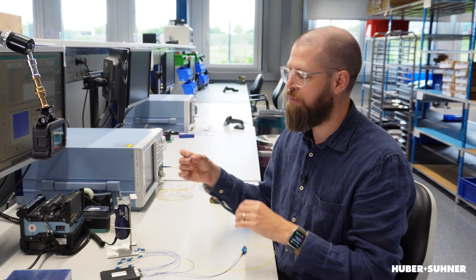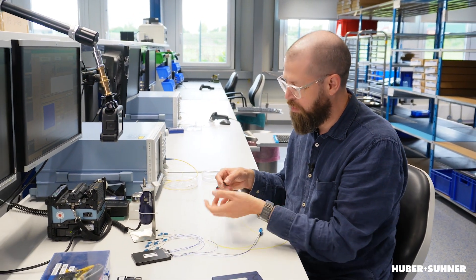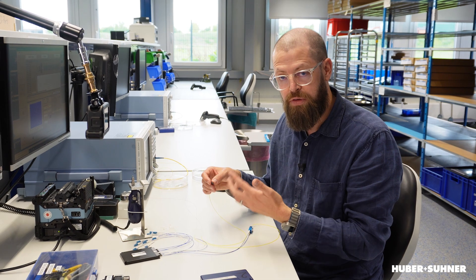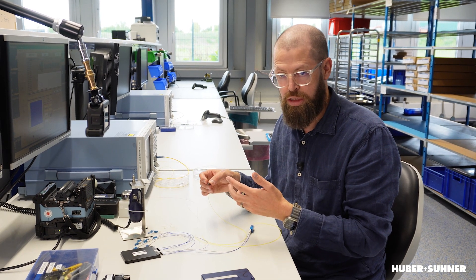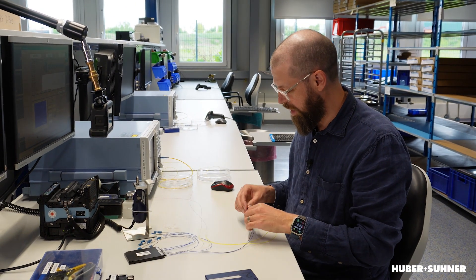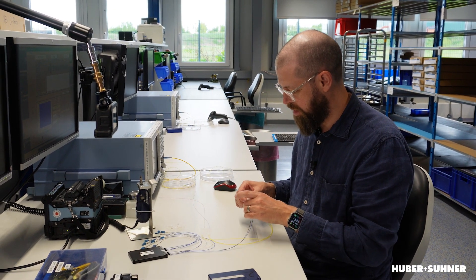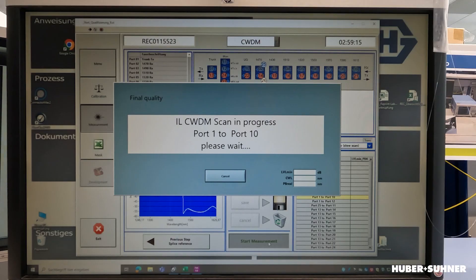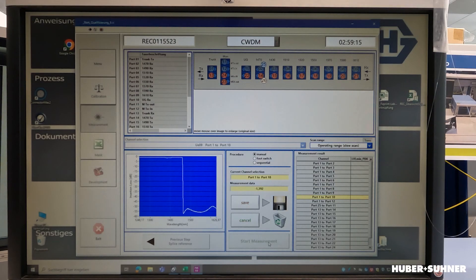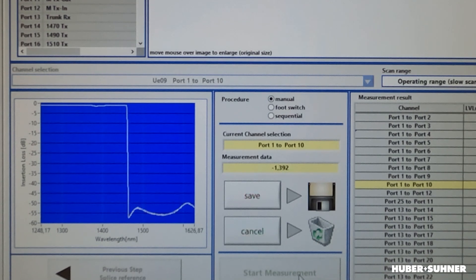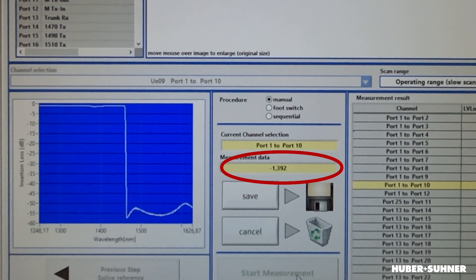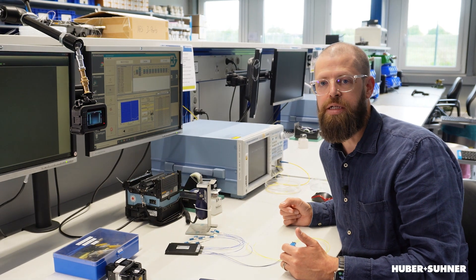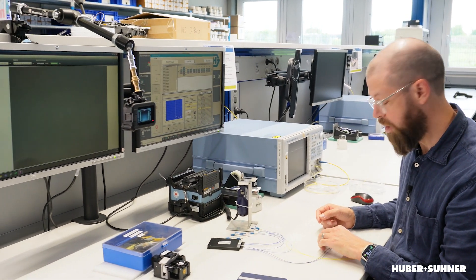What can happen is, if I remove a dust cap or anything like that, it can easily happen that I brush over the fiber connection. That actually has quite a significant impact — if I reconnect that and re-initiate a measurement, you can see the optical performance has decreased quite significantly: we're actually 0.3 dB higher insertion loss.